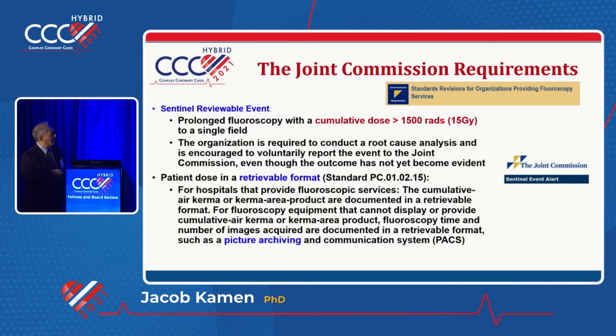The Joint Commission again came back and said, if someone gets 15 gray to the skin of the patient, it's a sentinel event. Sentinel event means it's an investigated incident, right? That means you have to investigate what happened. How did you give this much dose to the skin of the patient?